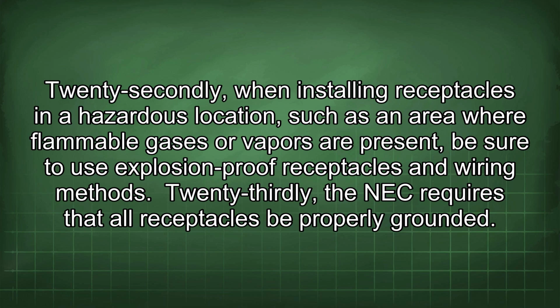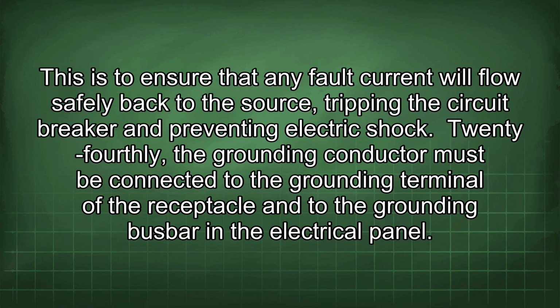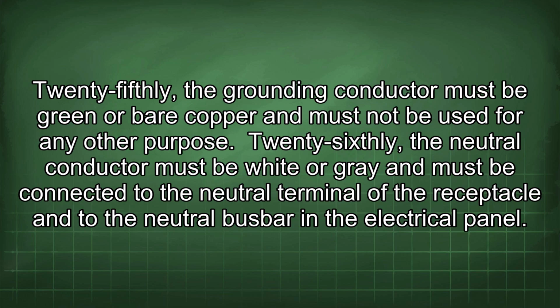23rdly, the NEC requires that all receptacles be properly grounded. This is to ensure that any fault current will flow safely back to the source, tripping the circuit breaker and preventing electric shock. 24thly, the grounding conductor must be connected to the grounding terminal of the receptacle and to the grounding busbar in the electrical panel. 25thly, the grounding conductor must be green or bare copper and must not be used for any other purpose.